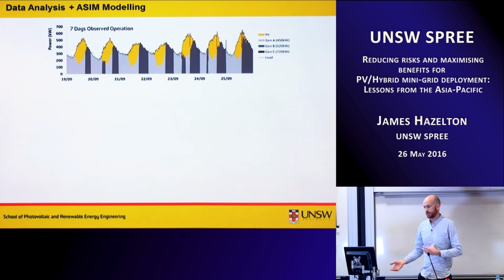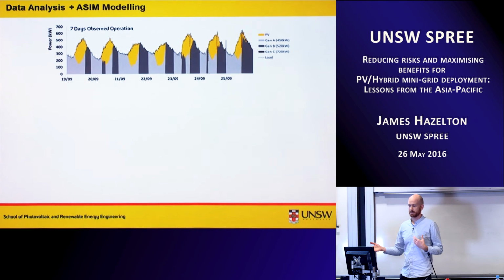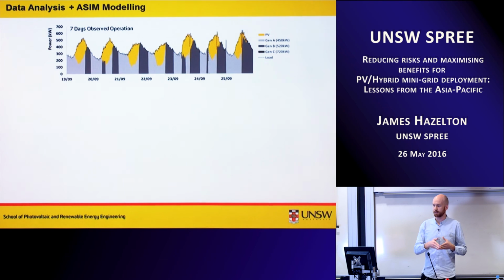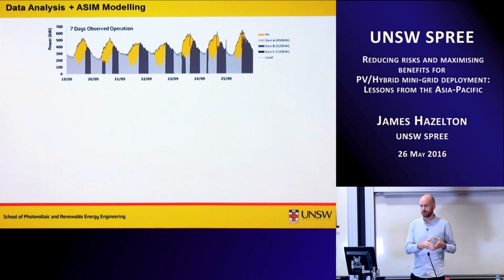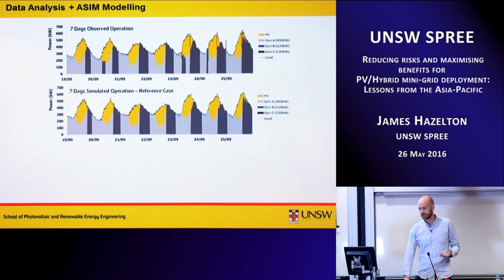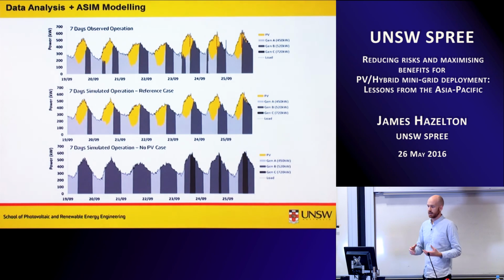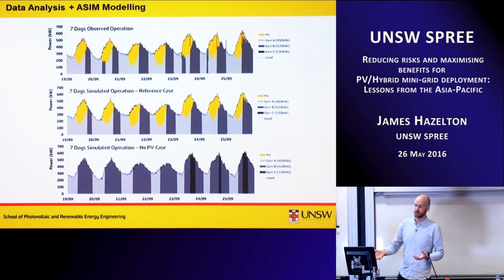What I used ASIM for was because, and this happens a lot in minigrid projects, there was no operating data to compare it to. So when you want to talk about the benefits and the risks in integrating PV, we couldn't really measure what was there beforehand. So I developed a reference case in ASIM and quite accurately modelled how the system would be performing. And then by tweaking some of these variables, I was able to take the solar back out and look quite accurately at how the system would have run had there not been solar.